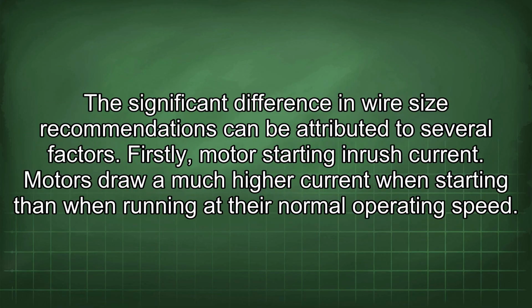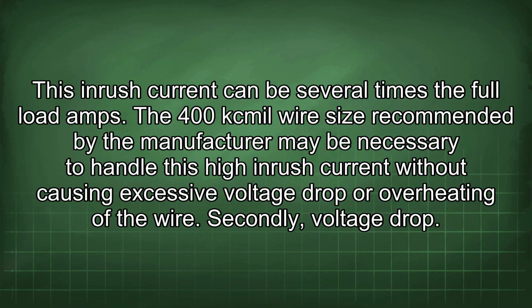The significant difference in wire size recommendations can be attributed to several factors. Firstly, motor starting inrush current. Motors draw a much higher current when starting than when running at their normal operating speed. This inrush current can be several times the full load amps. The 400 kcmil wire size recommended by the manufacturer may be necessary to handle this high inrush current without causing excessive voltage drop or overheating of the wire.